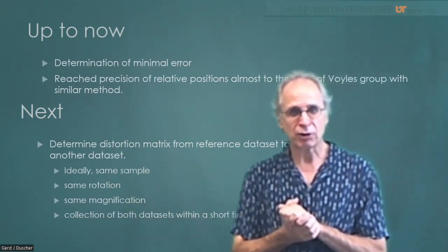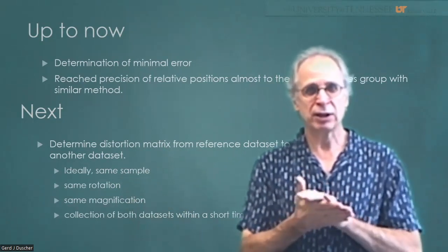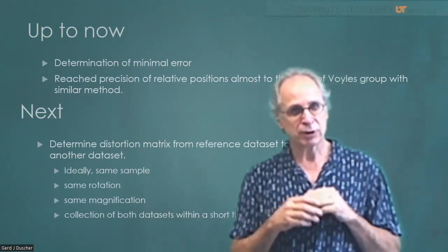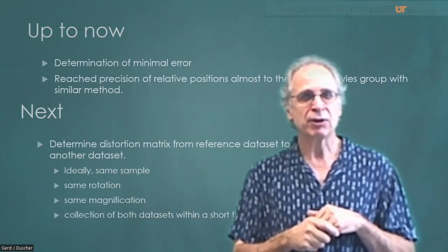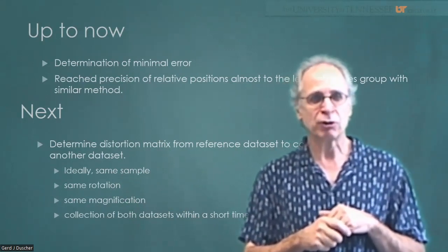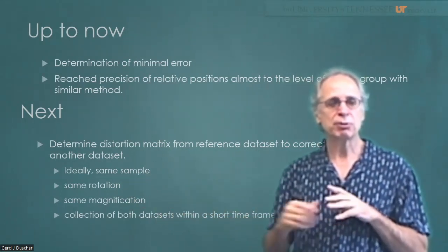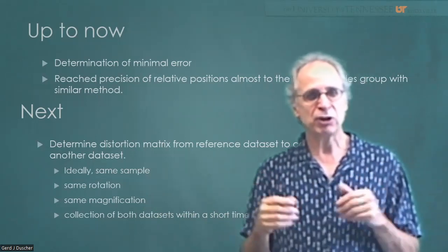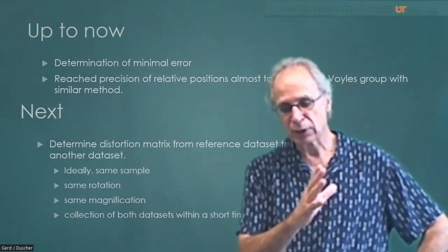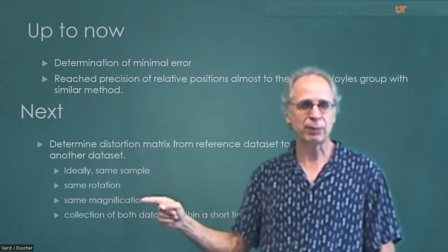The scan coils are not perfectly orthogonal, and the manufacturers of the electron microscopes have an engineering alignment that compensates for this non-orthogonality, and again, that is not going to be perfect. The magnification should be the same, or can be changed with moderation, but the closer you are to the same magnification, the better.